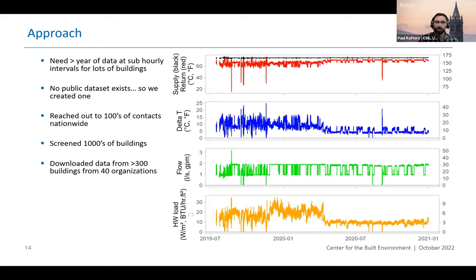Do you have a resource for setting up those standby loss tests? I would say just reach out to me directly and we'll walk you through the process. We have a paper that describes it in a lot more detail than the presentation. Every building is pretty unique in terms of what you actually will need to do to run that test, but conceptually it's: switch off all of the hot water end users, turn off all the air handlers, and just pump water around your heating system and maintain the temperature.